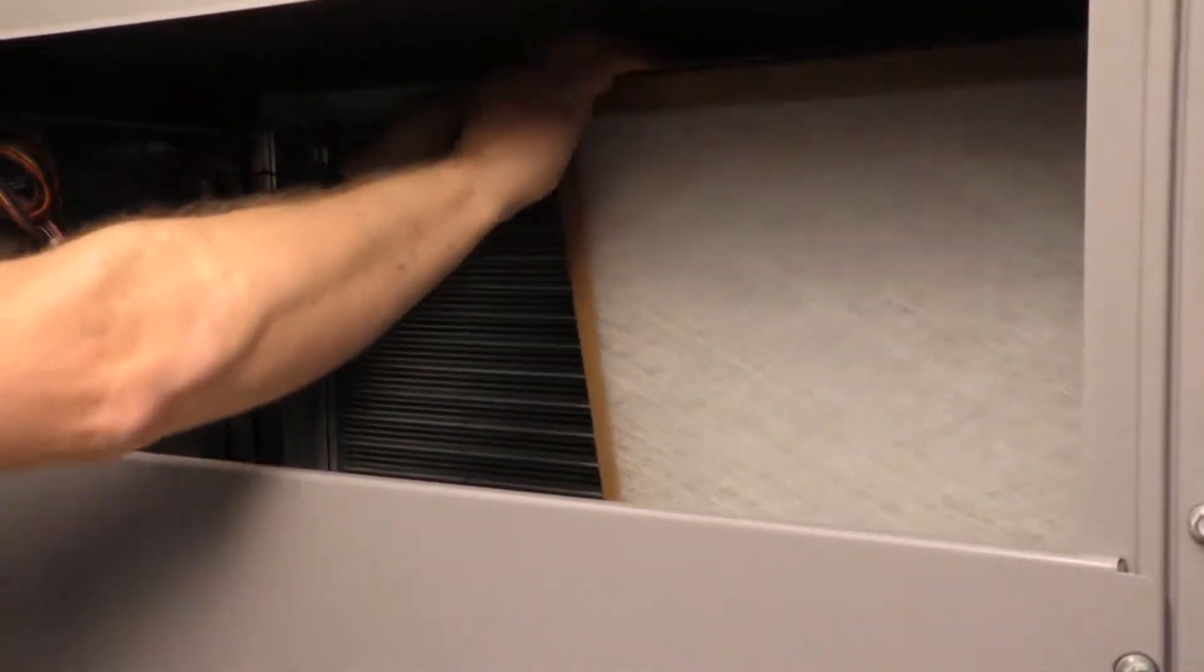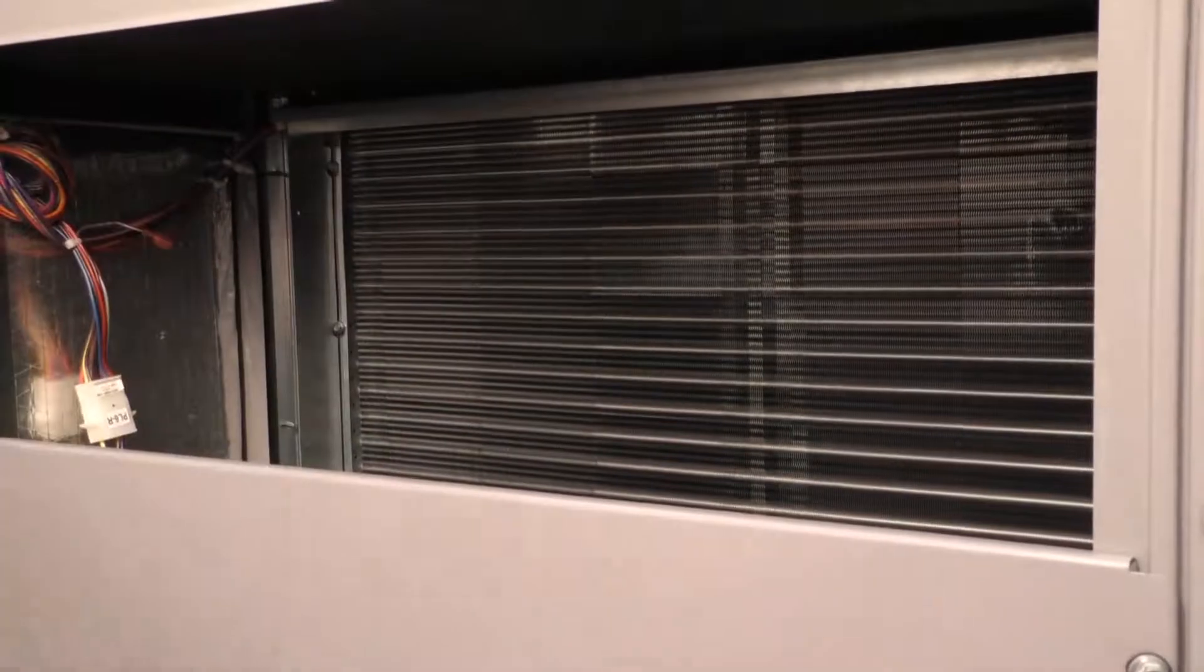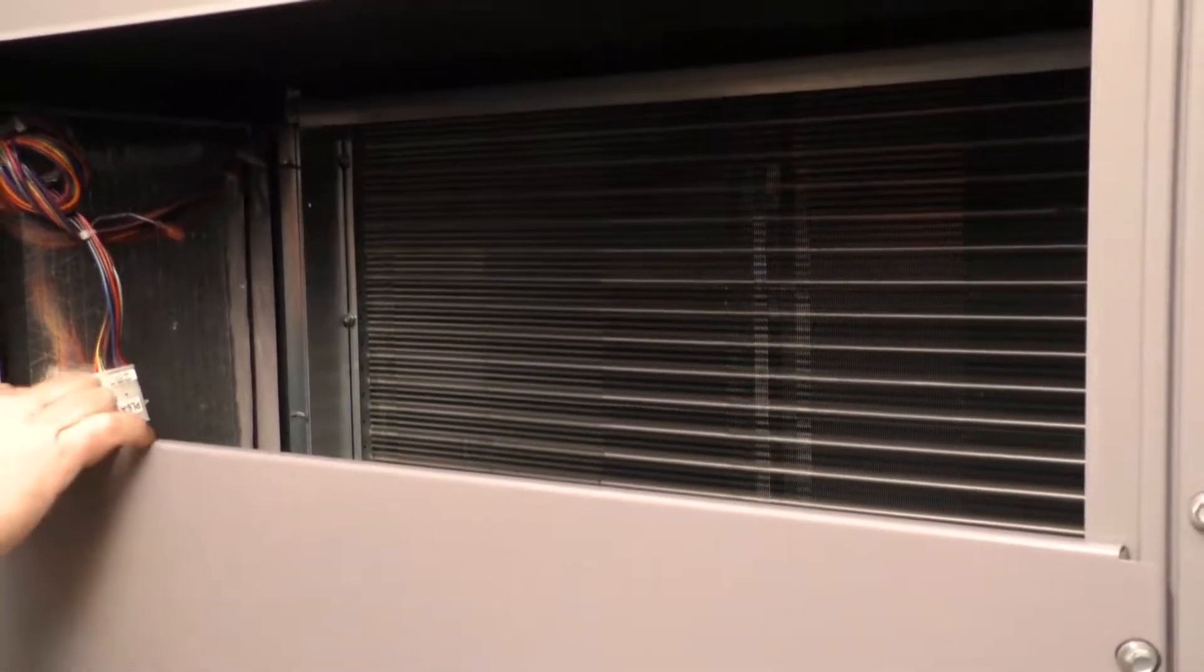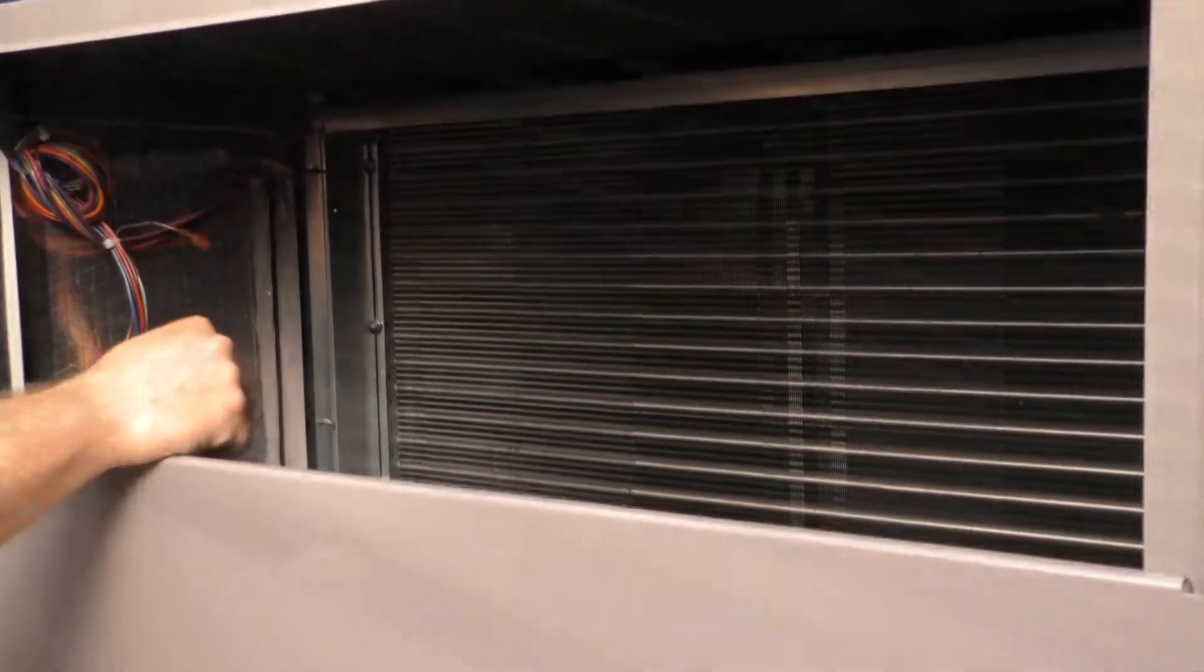With the removal of both of these filters, this allows us access for cleaning of the evaporator coil. It also allows us inspection of the condensate pan just below the evaporator coil. The replacement of them, we align the bottom of the return air filter in the blower rail, lifting the top rail, and simply slide them into place.